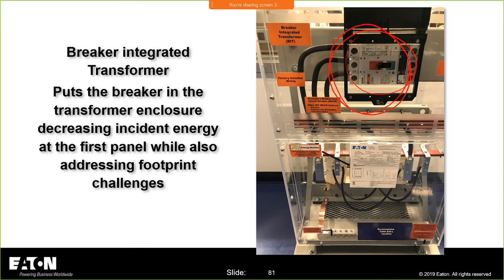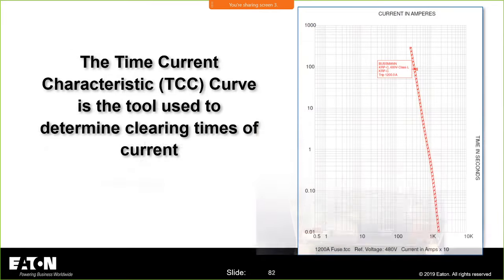You have the breaker that's integrated with the transformer. All right, very important, and key ways to help reduce the clearing times. Remember the time current characteristic curve, and we talked about this on Tuesday in our selective coordination discussions. So if everybody who was on this call followed through the week, you should know what a time current characteristic curve is, and you should understand that poor maintenance of overcurrent devices can impact these time current characteristic curves. Now you can say, well, Tom, the fuse guys always tell me there's no maintenance on a fuse. Well, yeah, you can't open it up. You can't do maintenance on a fuse, but you can check to make sure that it's not gotten wet. It didn't get water damaged. And you can check that maintenance has been performed on the switch that's enclosing it.